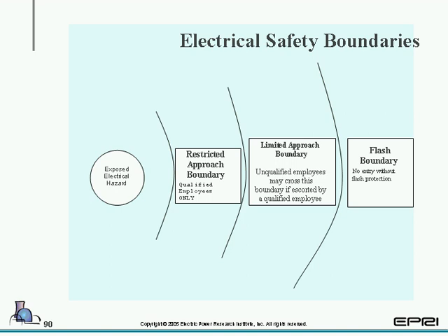This is kind of a graphic of the approach boundaries, the arc flash boundaries that are created, or that can be created as a result of one of these arc flash safety analyses. You have the exposed electrical hazard on the left, and to the far right you have an arc flash boundary, a limited approach boundary, and a restricted approach boundary. As you get closer and closer to the exposed electrical hazard, you get more and more restrictive.